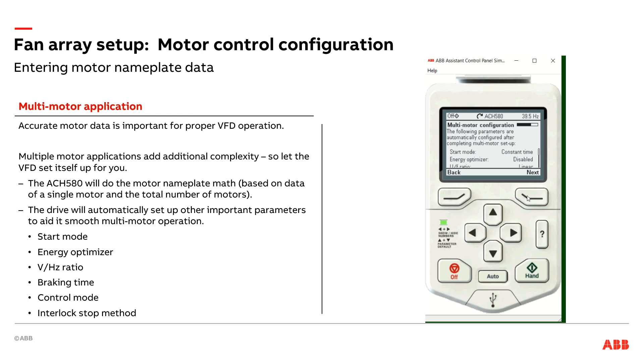In my younger days I taught a lot of startup classes dating all the way back to the ACH550. One of the questions I would get was: Tim, if I've got a multiple motor application, what do I need to do to the drive that's different from a typical single motor application? So let's take a look at what those are. First off, it changes the start mode from normally a flying start to what we call constant time — but really what that is, is it brakes the motors on start, gets them all lined up, and then starts them together.